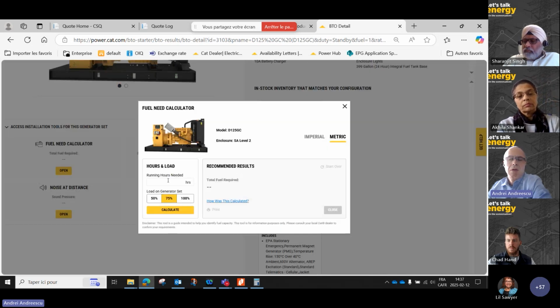Let's say we want to know how much fuel this generator will consume during 18 hours of running, at 50%, 75%, or 100% load. The tool can calculate the fuel consumed - 18 hours at 75% will be 612 liters of fuel.